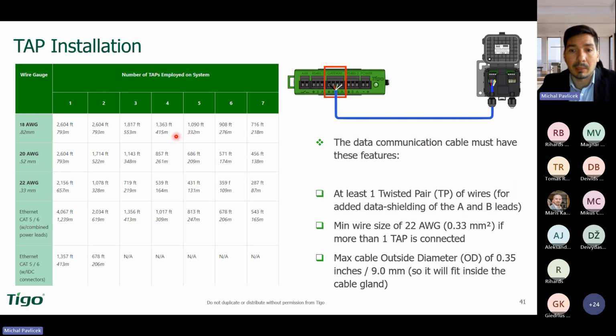When it comes to the length of the cable, of course, there are certain limits, but the cable can be up to 9 millimeters in diameter. We can have pretty thick communication cables, and as you may see, we can go even with one tap up to 793 meters with standard AWG cable, or if you go with a more robust cable like Cat5/6, you can go even to 1.2 kilometer long cables. The limitation here is because of the voltage drop. That's like in standard communication, so nothing specific.